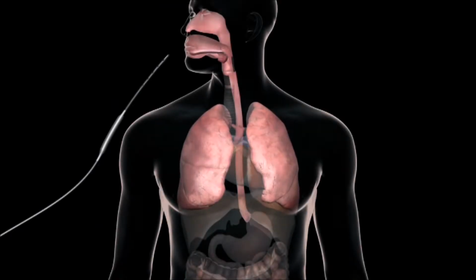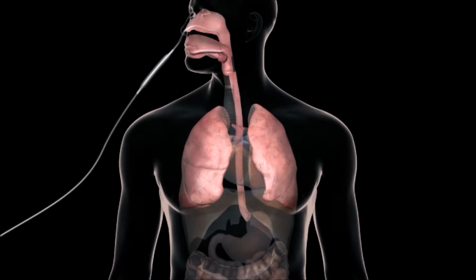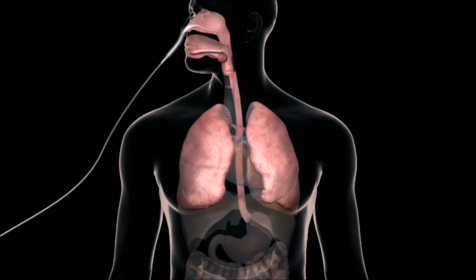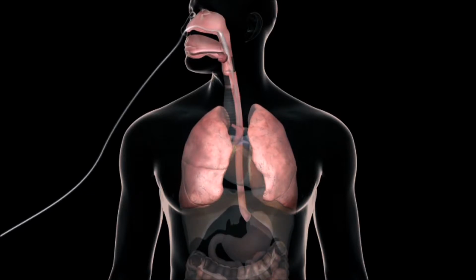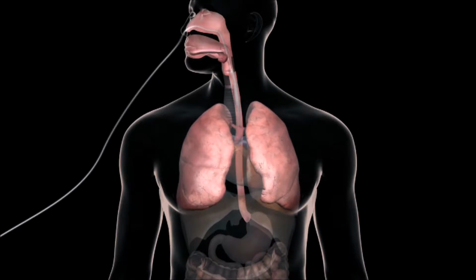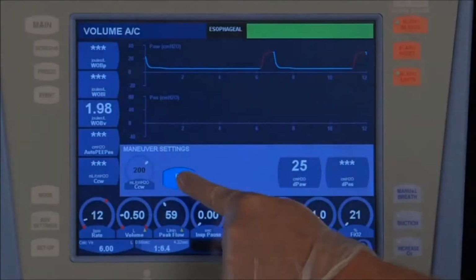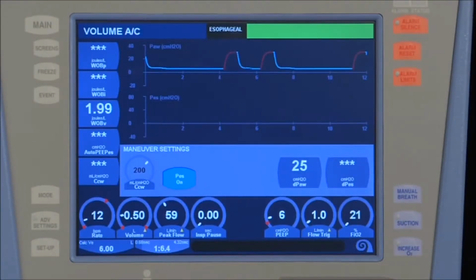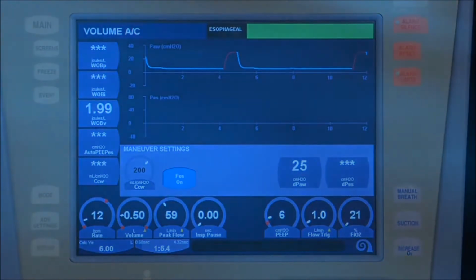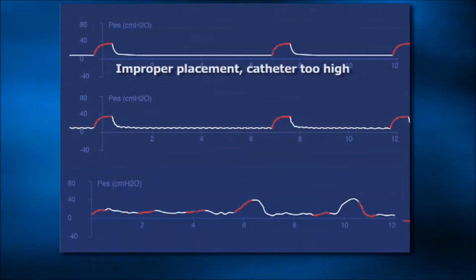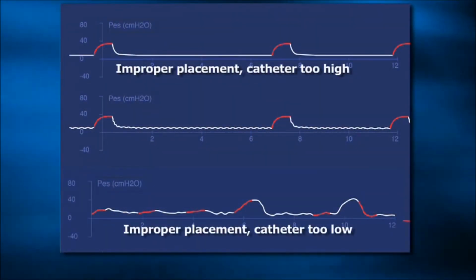For insertion of the SmartCath nasogastric balloon, an approximate level of placement can be made by measuring the distance from the tip of the nose to the bottom of the earlobe, and then from the earlobe to the distal tip of the xiphoid process. The esophageal pressure on button can be activated during insertion to allow the operator to confirm placement of the balloon. Once the esophageal pressure monitor is turned on, monitored displays of waveforms are seen as the catheter is advanced, highlighting proper placement in the esophagus.